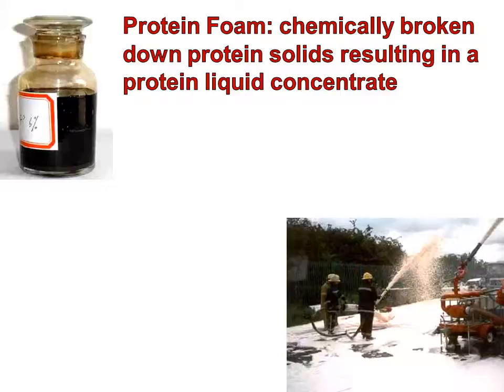A protein foam chemically breaks down protein solids, resulting in a protein liquid concentrate. It's low expansion, with excellent water retention capabilities, high heat resistance, and reignition resistance. Requires a close approach by firefighters.